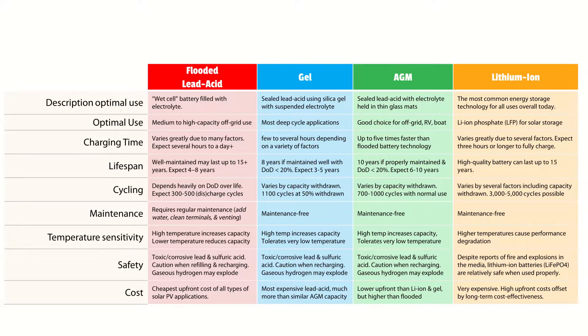Lithium ion batteries can store almost four times more energy than lead acid batteries, with energy densities around 150 watt hours per kilogram compared to lead acid batteries at around 40 watt hours per kilogram. These batteries also differ in terms of their usable energy: it's recommended that you use around 85% of a lithium ion battery's capacity, or only 50% of a lead acid battery. Dropping below these recommended thresholds could damage or significantly shorten the lifespan of the batteries.